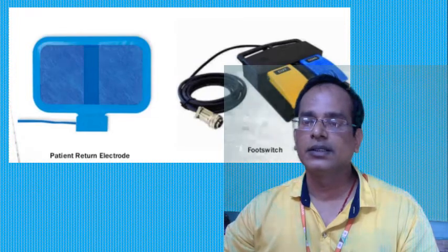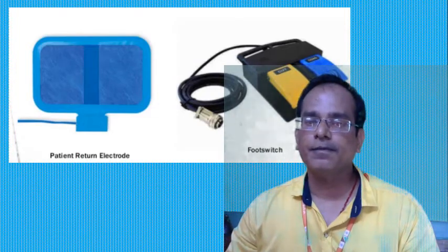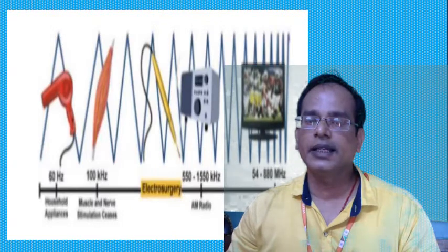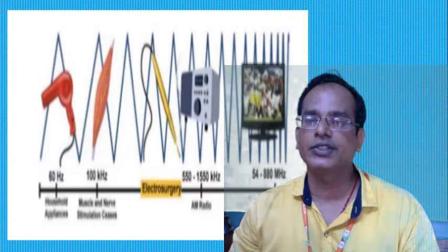And so here you are seeing electrosurgery and electrocautery. Electrosurgery is the application of high frequency, that is radio wave frequency, alternating electrical current to biological tissue for thermal destruction of tissue through dehydration, coagulation or vaporization.